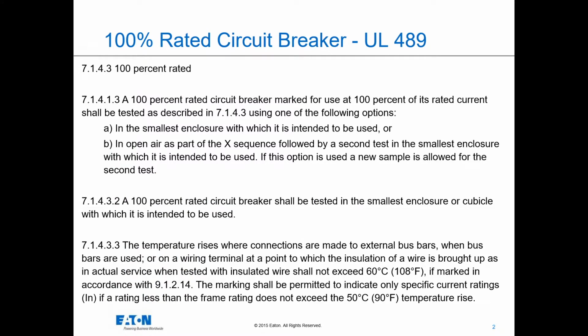100% rated circuit breaker marked for use at 100% is in the smallest enclosure. It's both the assembly and the breaker, so the breaker and the assembly go together. So look at how we test this device. We have a 100% rated circuit breaker marked for use at 100% rated. It has to be tested in the smallest enclosure within which it is intended to be used, or in open air as part of an X sequence followed by a second test with the smallest enclosure. 100% rated circuit breakers shall be tested in the smallest enclosure or cubicle.